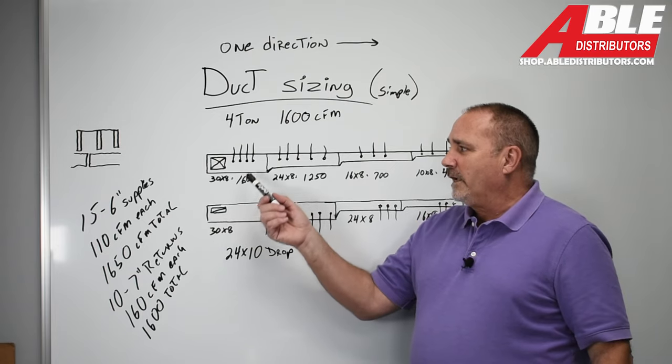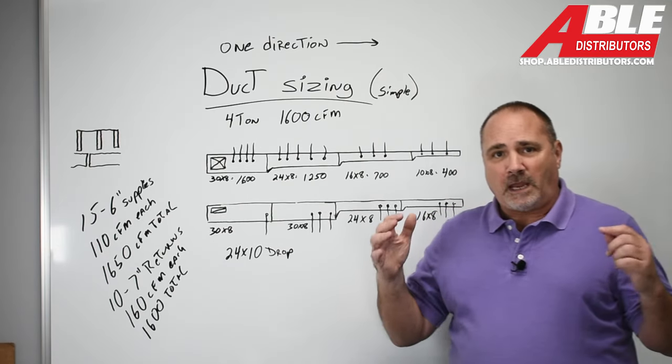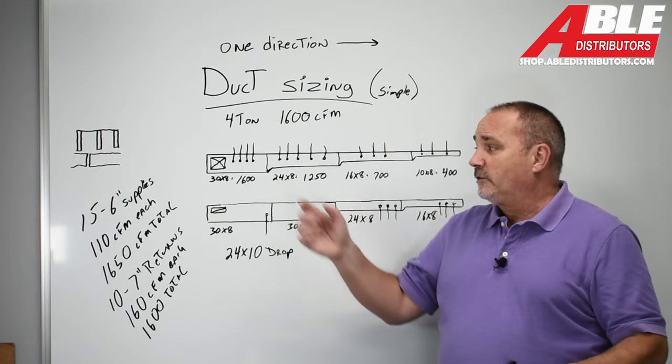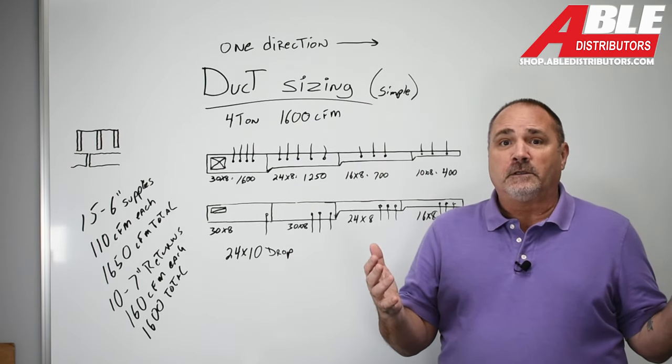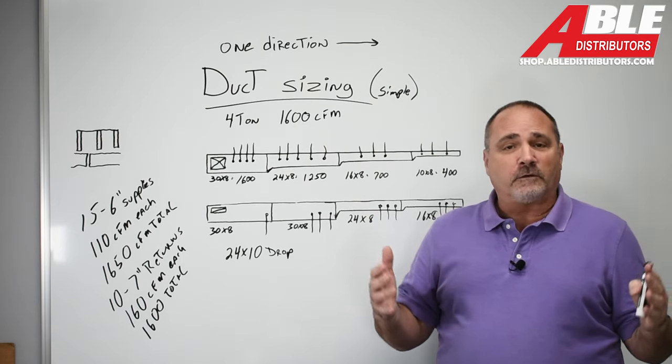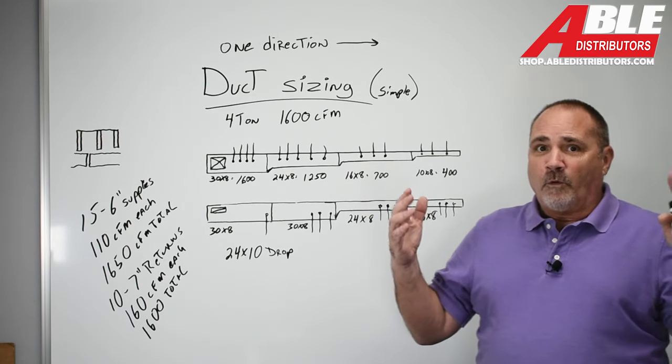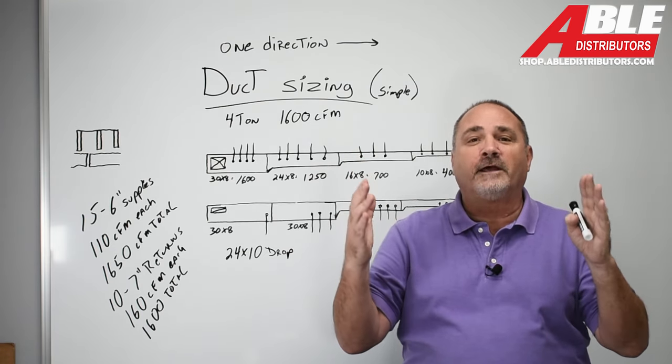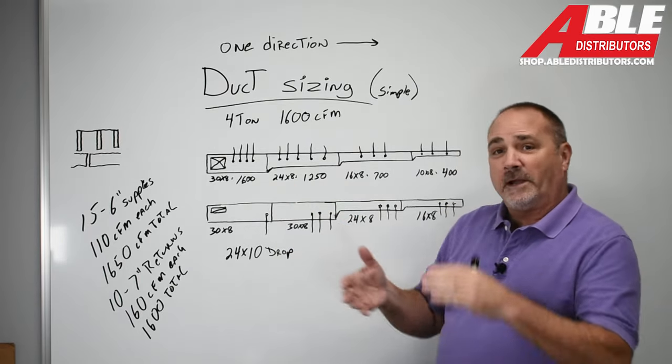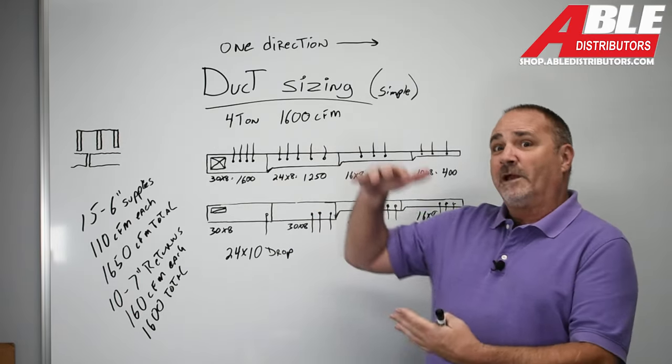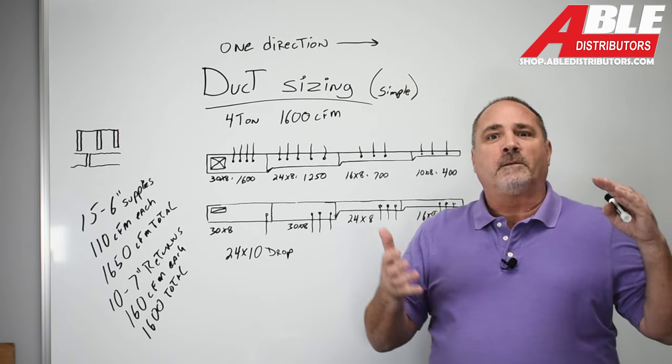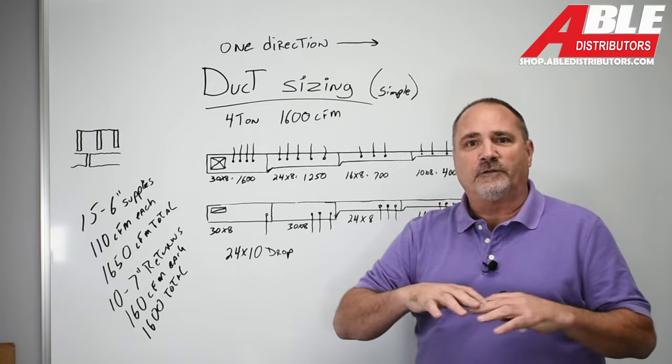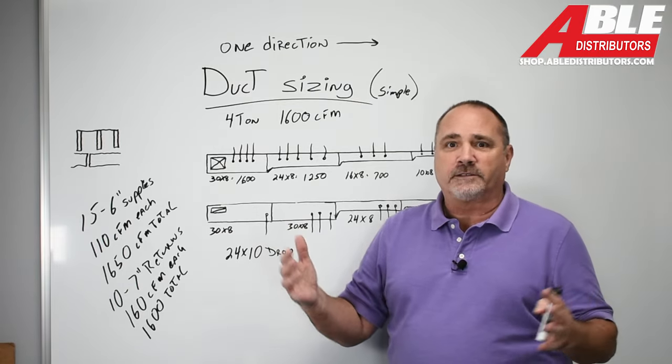I started out in 30 by 8. That first piece of duct has to be capable of the full 1,600 CFM. Anything less than 30 by 8, it's just not going to do it. You know, I run across a lot of guys when I go to jobs and I ask them, what made you choose that size duct? And they say it fit. I don't like that answer. Either go 24 by 10, go 20 by 12, go 30 by 8, do something to make sure that you have enough in your first piece to handle the entire load, the entire CFM. It's where you got to start.